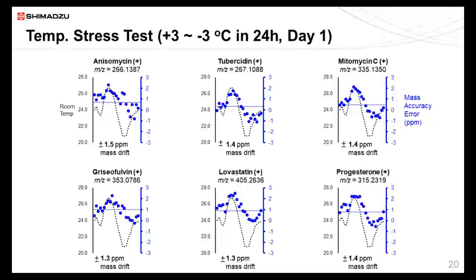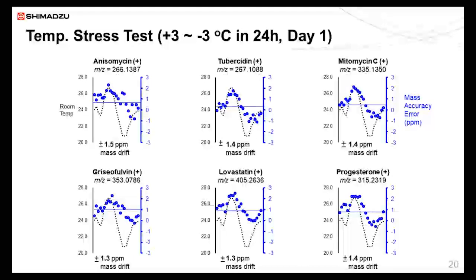And this is the result of the temperature stress test, plus or minus 3 degrees in 24 hours. And we're showing here 6 compounds, and the black trace in dotted line shows the temperature change, up by 3 degrees, down by 6 degrees, and up by 3 degrees again. And these are the actual measured temperatures in this controlled environment. And the blue dots represent the mass accuracy, the mass error in ppm, of the individual mass measurement over the 24 hours.